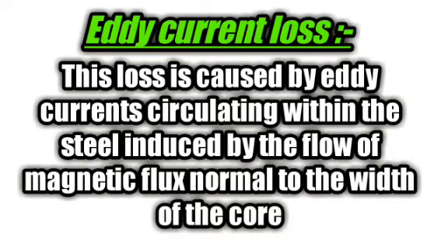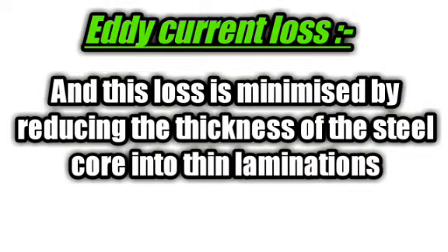Eddy current loss. This loss is caused by eddy currents circulating within the steel, induced by the flow of magnetic flux normal to the width of the core. This loss is minimized by reducing the thickness of the steel core into thin laminations.